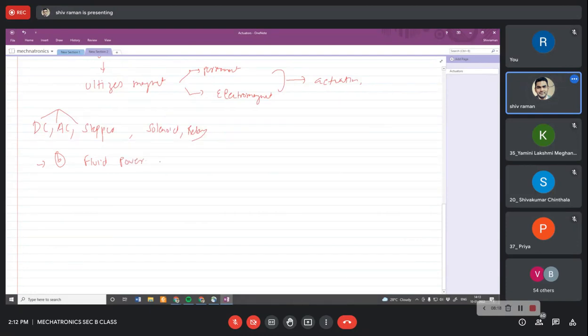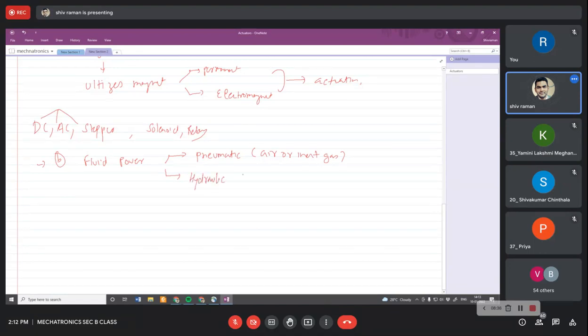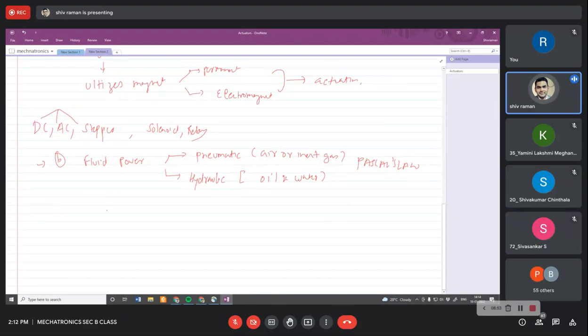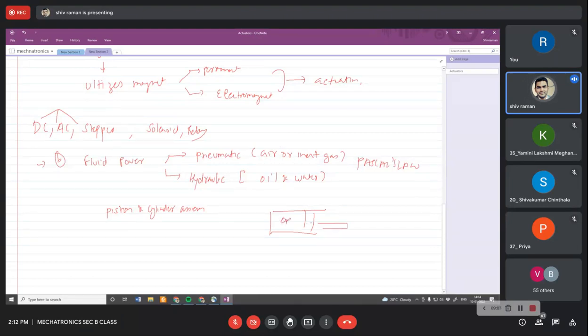For fluid power actuators, there are two types: pneumatic and hydraulic. Pneumatic utilizes air — pressurized or compressed air, or inert gas. Hydraulic uses oil and water. The major working principle is Pascal's law. Actuation is realized through a piston and cylinder assembly: based on the variation in pressure (delta P), the piston moves and this motion is transferred via a rod to the required system.